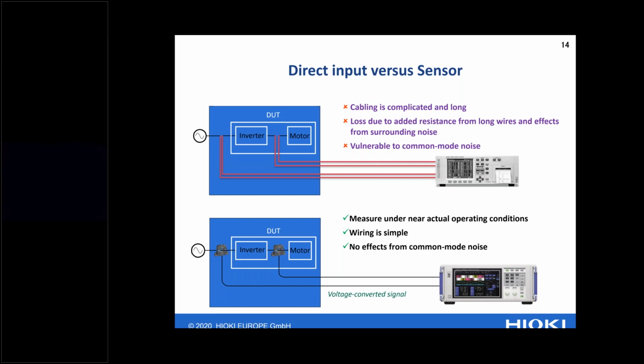When you go directly into the power analyzer, there will be heat generation, which causes degradation, meaning more inaccurate results. A second problem with a direct connection is that long wiring causes, from a physical point of view, higher resistance, which also causes problems and external effects when you want proper measurement results displayed.